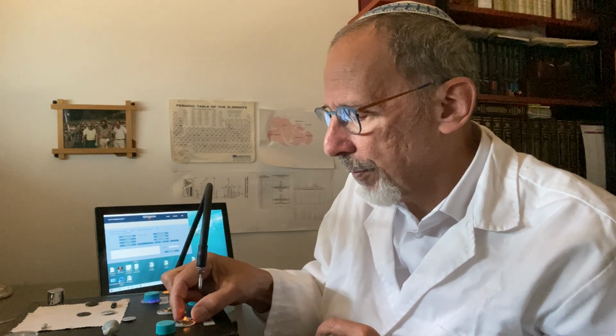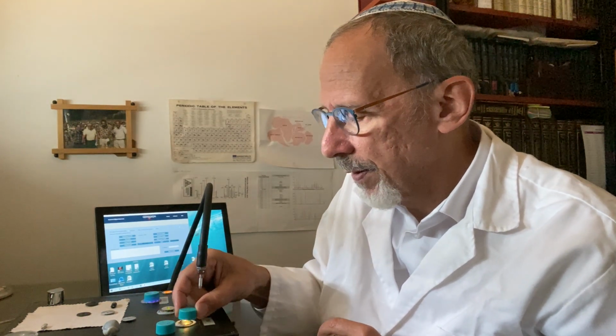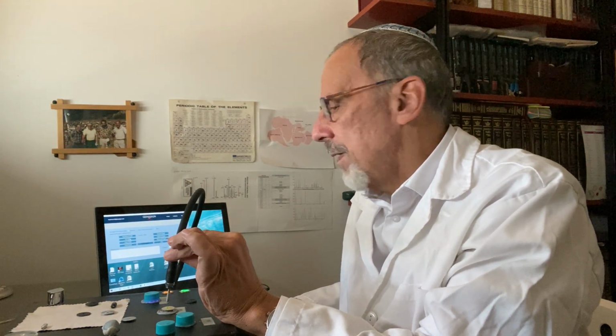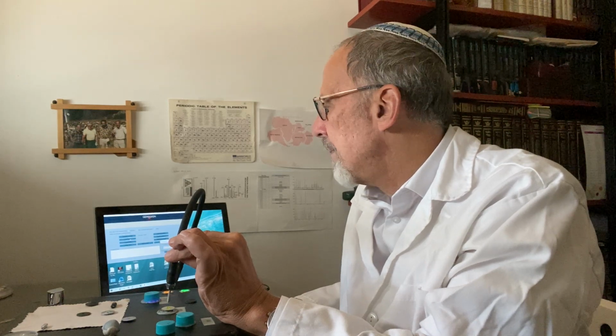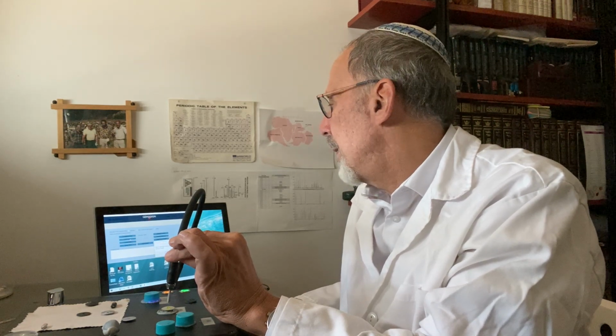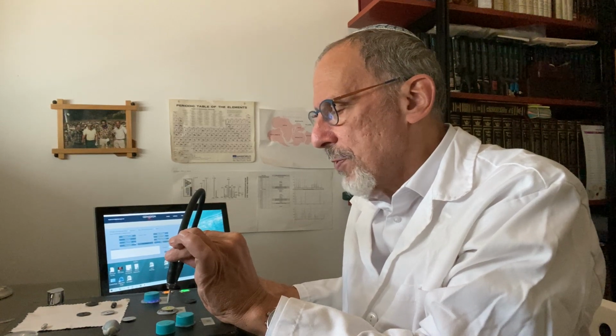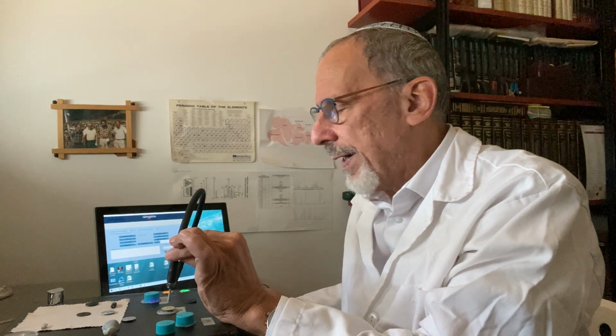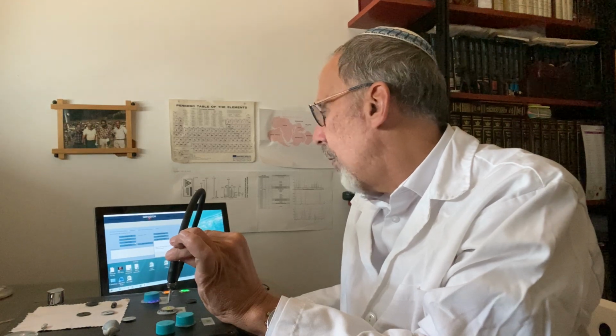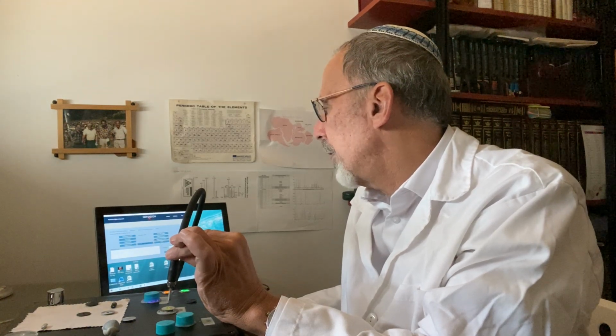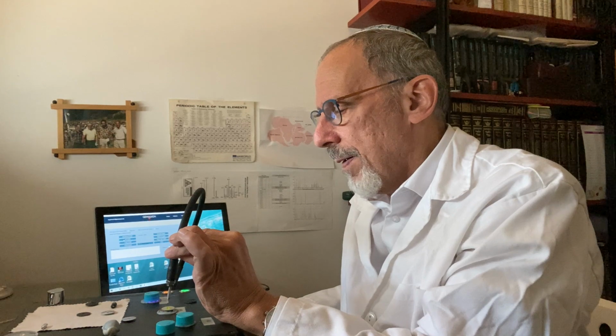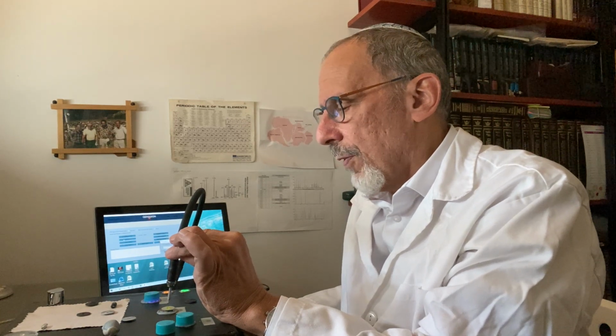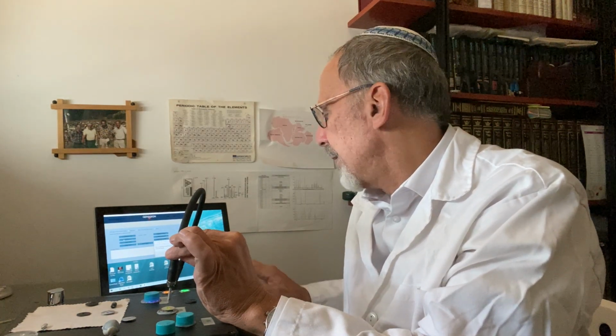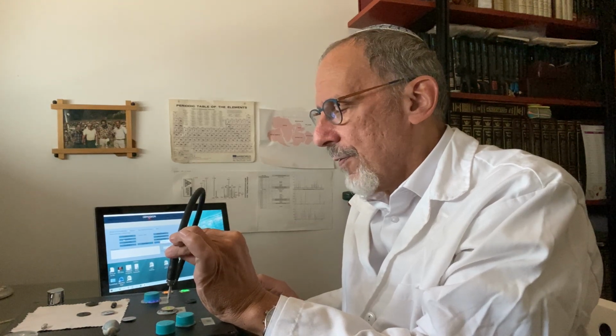Next, I'm going to do a capture of the UV by doing the same kind of thing. Just hold it about 1 centimeter above it and click UV. And it says it's saturated, which means a little bit too much light got into the detector. I can always move the probe a little bit further away, and therefore less energy will get into the detector, and it'll give us a nice spectrum.